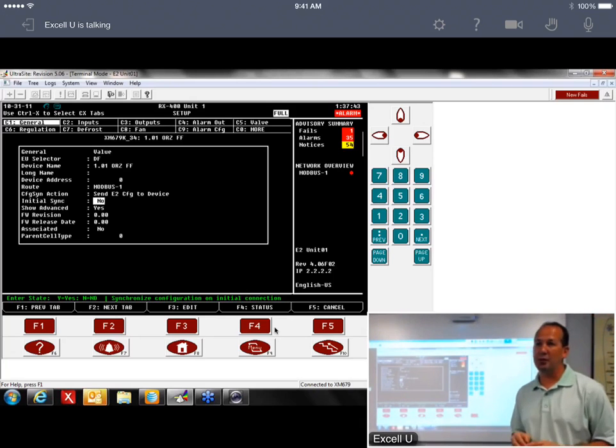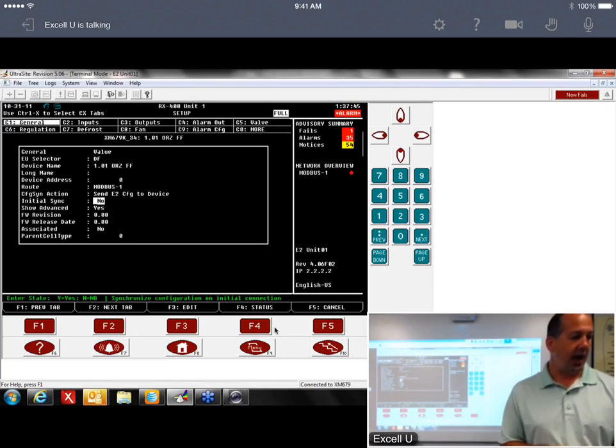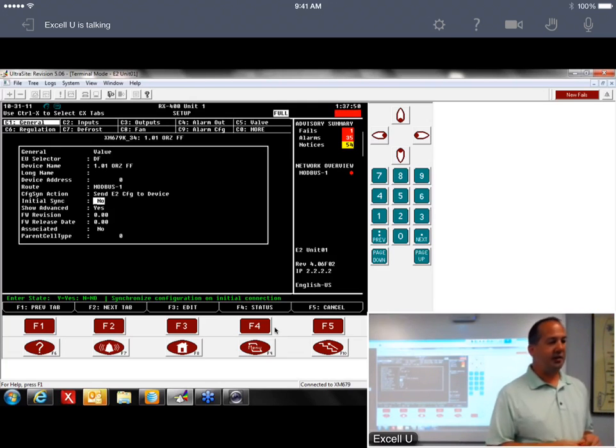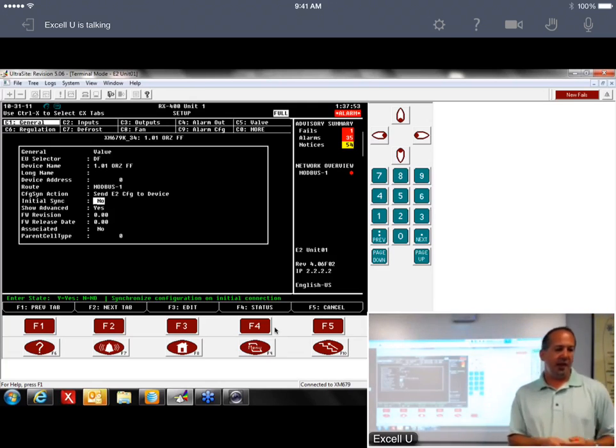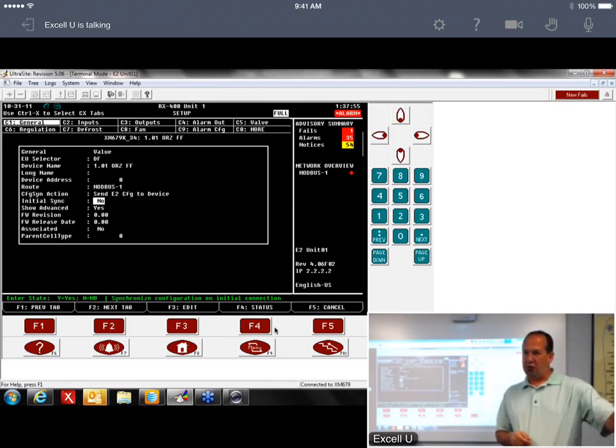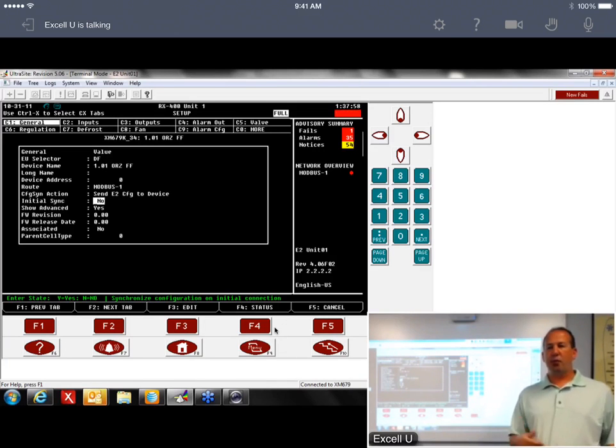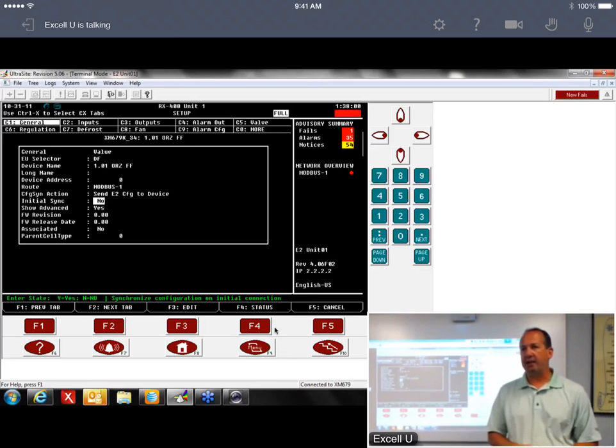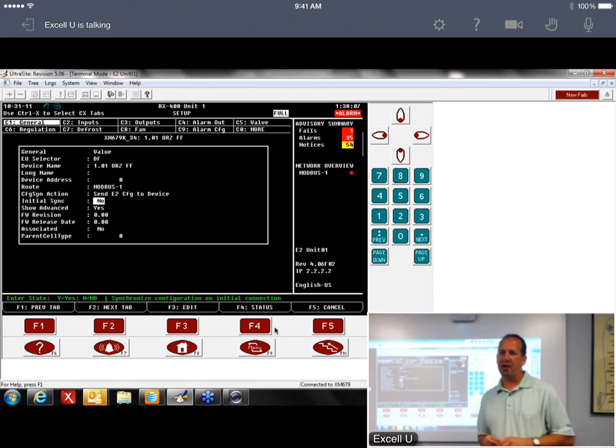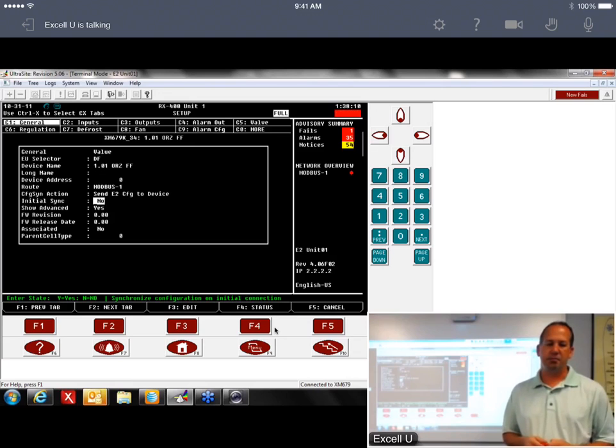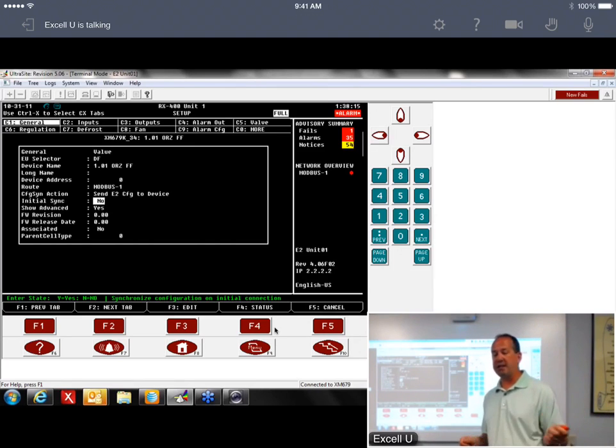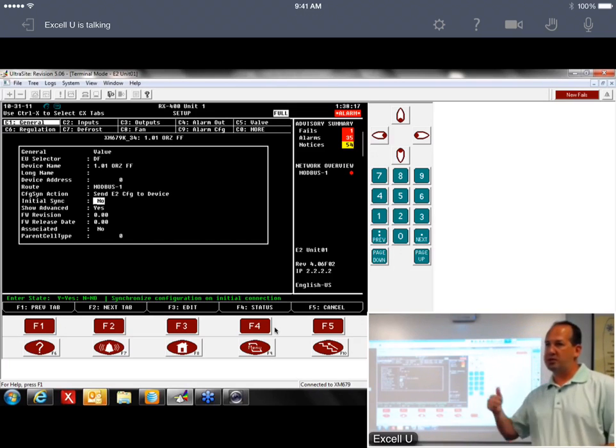So if you were to program this with a hotkey, you've got your program in it, or you programmed it from the display, which I really wouldn't suggest trying to do, then what happens is you've got everything loaded into the device, you bring it online, and it says okay, here's everything I had. I wouldn't do that, even if you use a hotkey, because there's too many parameters that reside in that device that you might have missed. So even if you program it from a hotkey, I still don't want those parameters being pushed into the E2.